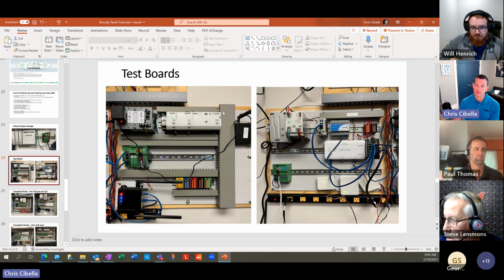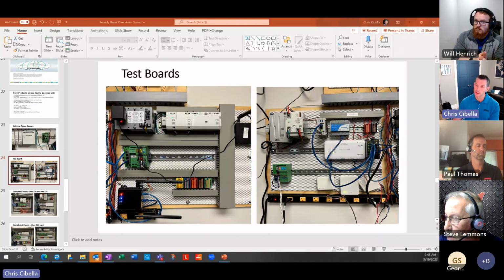It's got some of the DIN rail, the wire duct, and then these are PT Fix distribution blocks. So typical application, actually this page over here on the right side here, this is a typical application coming out of the power supply. You would go into say your plus and your minus on your 24 volt circuit and go into these little PT Fix blocks. Because as you can see here, they're pretty thin, but you have 19 points of contact there. So very inexpensively and in a space saving fashion, you get some really nice distribution blocks on there. And you can color code these. I think there's 13 different colors.